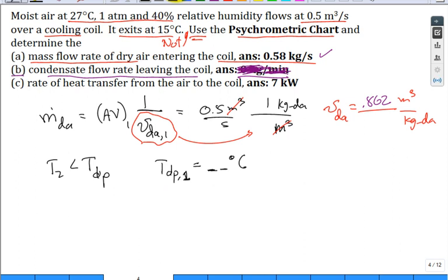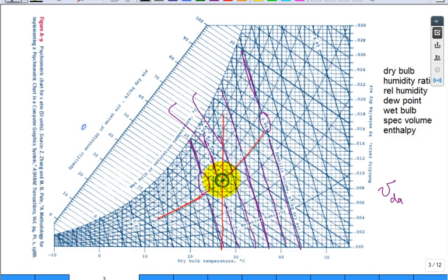All right, so let's go ahead and stop this. I'll just close it out. And I'll go back to the psychrometric chart. And at this point, that's the point of interest. What we do is we conceptually say, do not increase or decrease the amount of moisture in that air, but start to cool it and cool it and cool it until it gets to be saturated air. At that point, you cannot cool it anymore without some of it dewing out. That's called the dew point temperature.